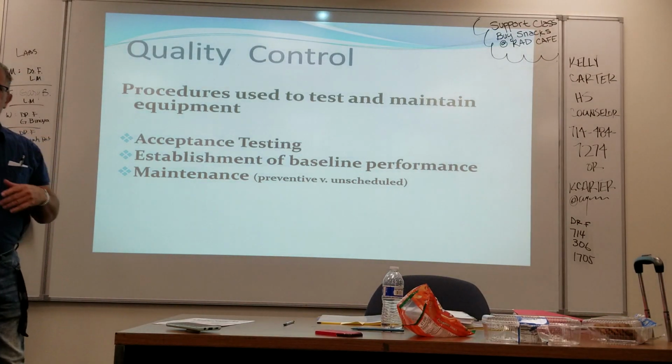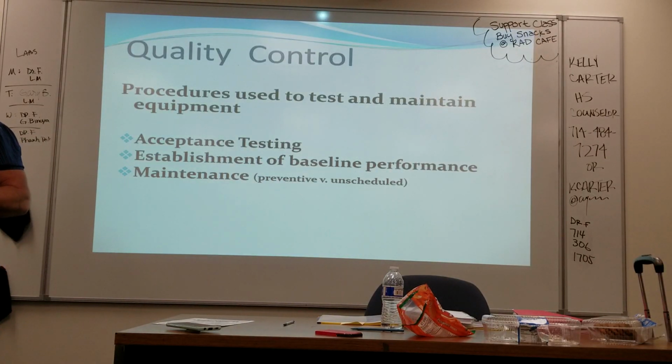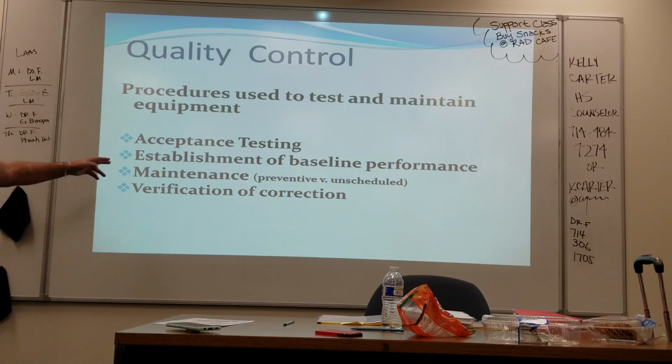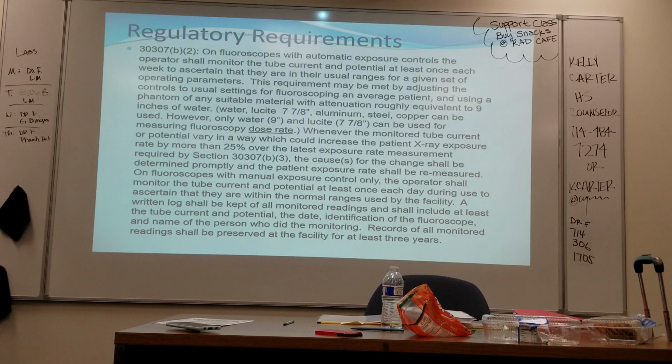Preventive is usually things that are done annually, quarterly, and semi-annually, and that's either performed again by the vendor, or if you have in-house service, some of those they're going to perform. There's also annual testing that medical physics has to do for particular pieces of equipment. If there's a problem, then there also has to be verification testing showing that it's been corrected and that it's done by a person that's recognized by the accrediting agencies or ACR, if you're through one of their programs, can do.